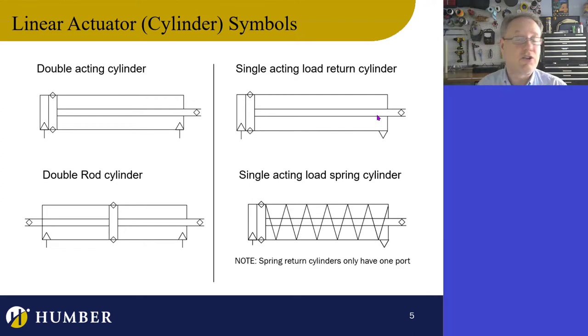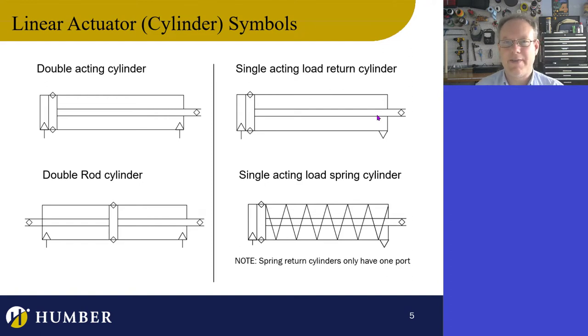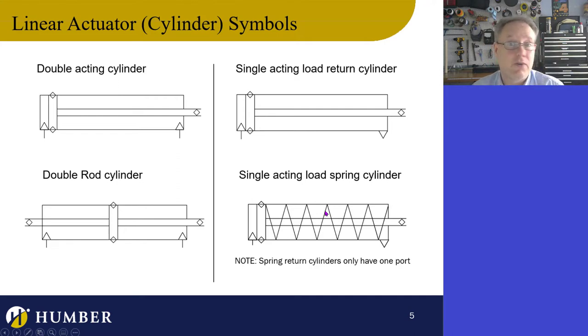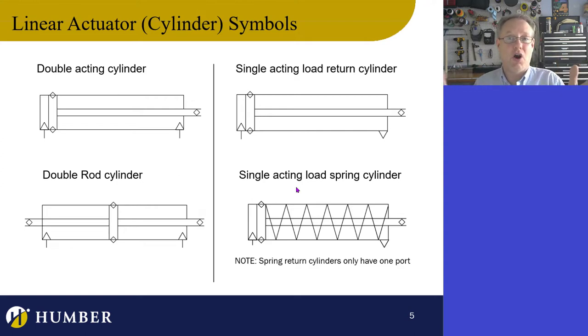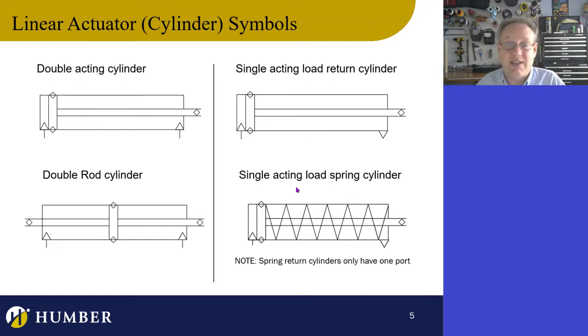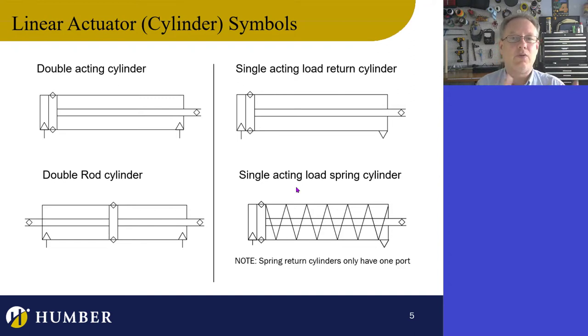The single-acting spring-return cylinder has a spring for retraction or extension — both versions are available. You can order one with a spring in retraction or extension. When calculating forces, the spring force must be taken into consideration. There are lots of applications for these — for example, when the load isn't strong enough to retract the cylinder quickly enough, the spring helps. We'll look at those applications as we go through design processes in this course.